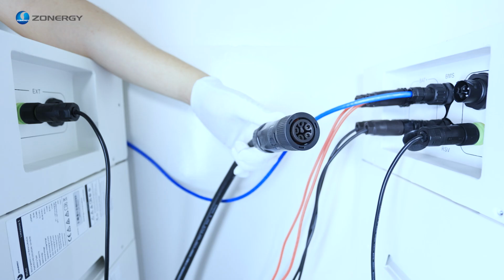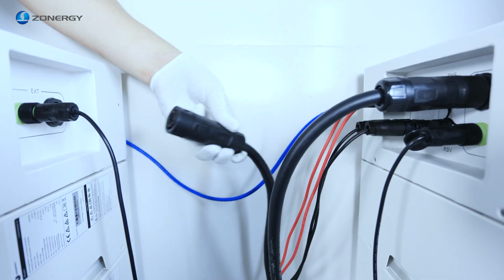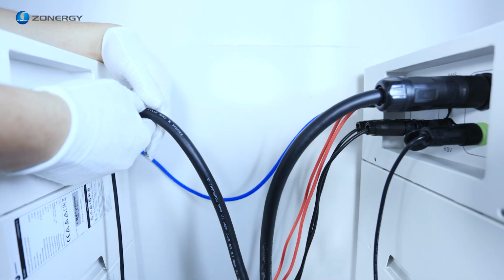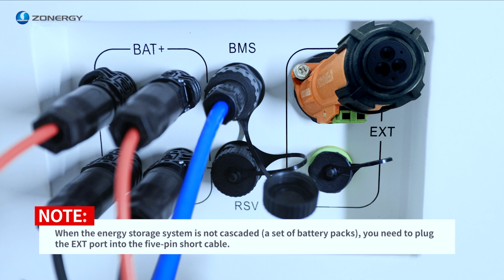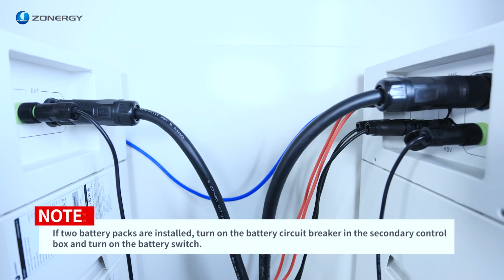EXT power cables connect EXT ports between battery packs. Note: when the energy storage system is not cascaded, a set of battery packs, you need to plug the EXT port into the 5-pin short cable. If 2 battery packs are installed, turn on the battery circuit breaker in the secondary control box and turn on the battery switch. Check the energy storage system before powering on.